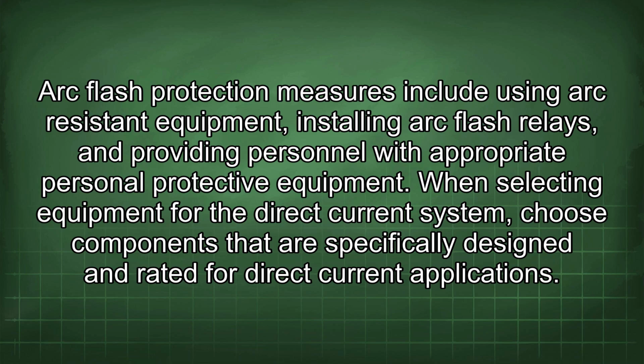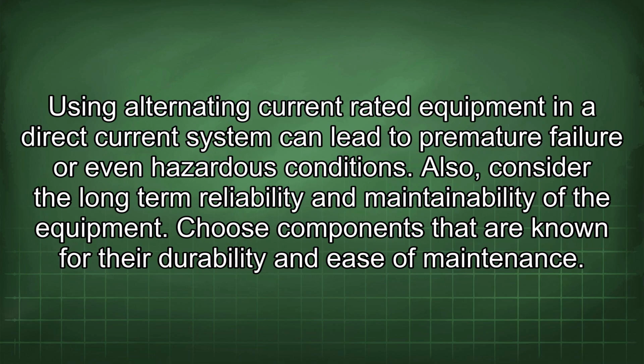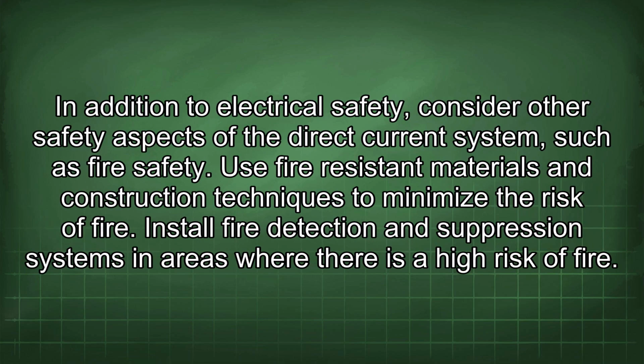When selecting equipment for the direct current system, choose components that are specifically designed and rated for direct current applications. Using alternating current rated equipment in a direct current system can lead to premature failure or even hazardous conditions. Also, consider the long-term reliability and maintainability of the equipment. Choose components that are known for their durability and ease of maintenance. In addition to electrical safety, consider other safety aspects of the direct current system, such as fire safety. Use fire-resistant materials and construction techniques to minimize the risk of fire. Install fire detection and suppression systems in areas where there is a high risk of fire.